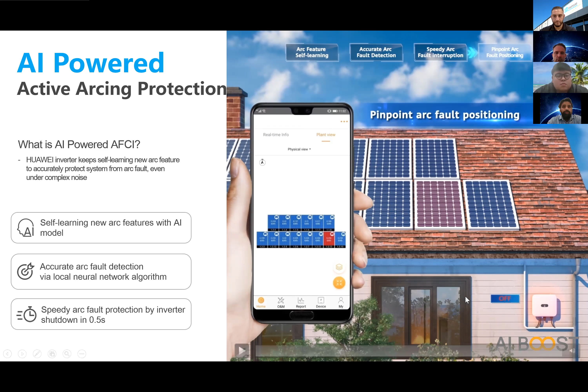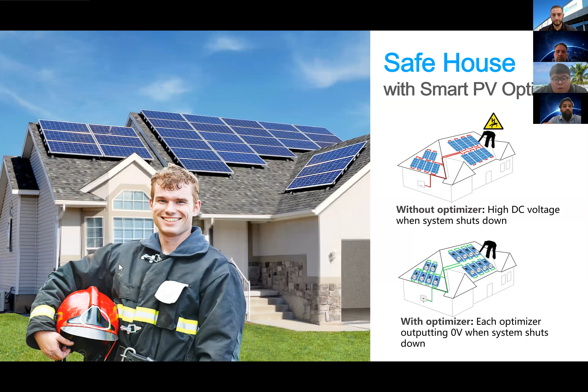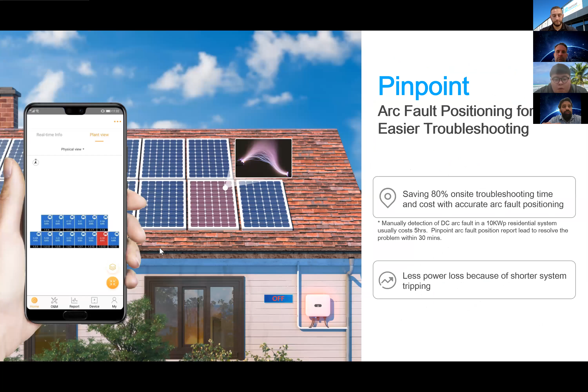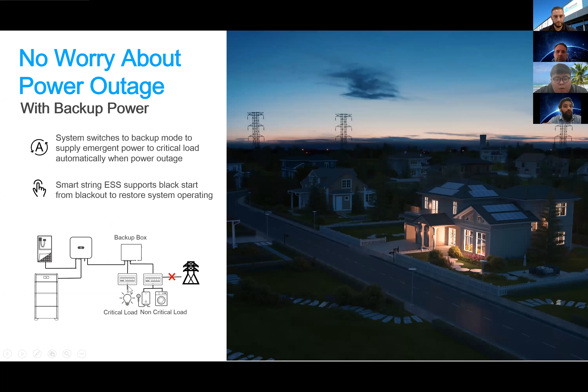AFCI is enabled by default, with disconnection in less than 2.5 seconds as per the standard. Internal test results are less than 0.5 seconds. And with a full optimized solution, which is pretty standard with optimizer solutions, you can reduce the voltage to a safe voltage level, 0 voltage in our case, just by switching off the AC of the inverter. And the backup box feature: a separate backup box when you have a battery installed with the Huawei L1 or M1 series, you can install a separate backup box and rewire critical loads through it.